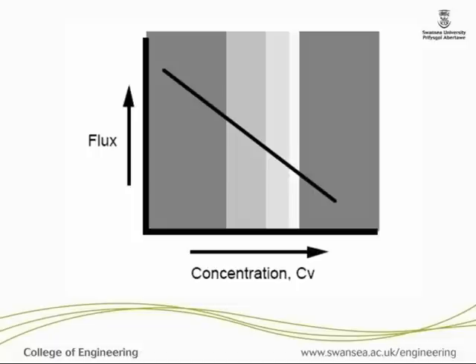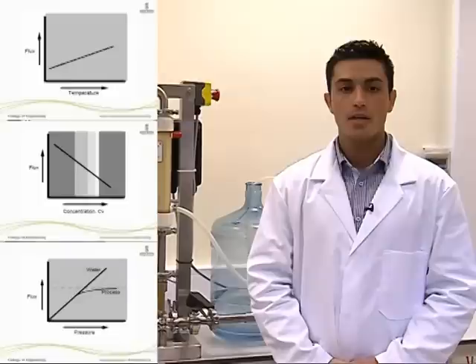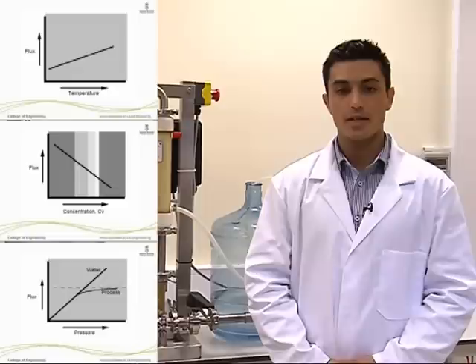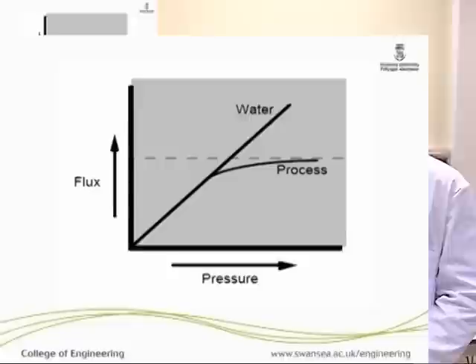Secondly, in terms of concentration, it is important to avoid concentration gradients. If the volume to be processed is higher than the capacity of the system, keep the feed tank full until all the volume is processed. Logically, higher concentration will create lower fluxes and longer operation times. Typically, this system can be used for suspensions with up to 20% solids. However, a more conservative approach is recommended — maximum 15% solids should be used.